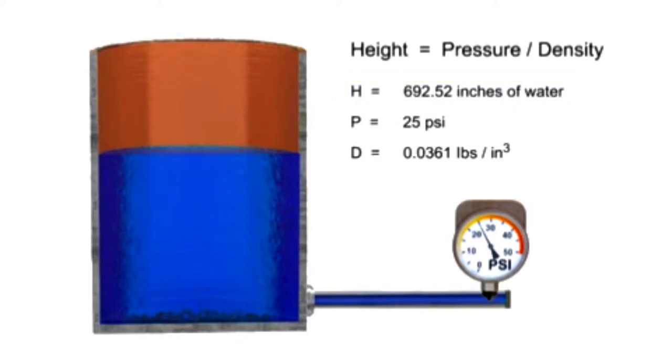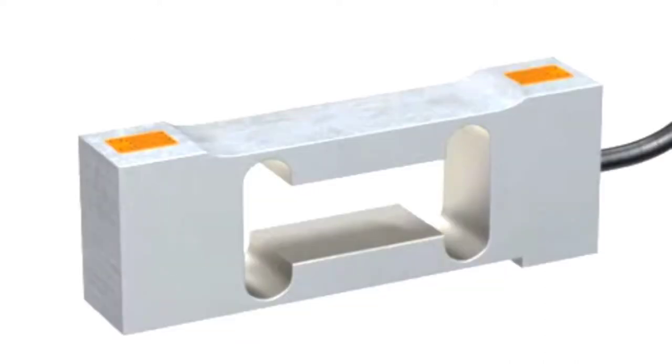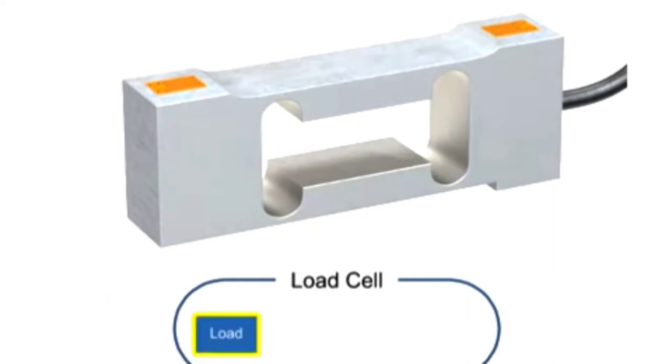Another method of calculating the level of material in a vessel by weight is using load cells. Load cells are comprised of a strain gauge bonded to a support and convert a force or load to an electrical signal.